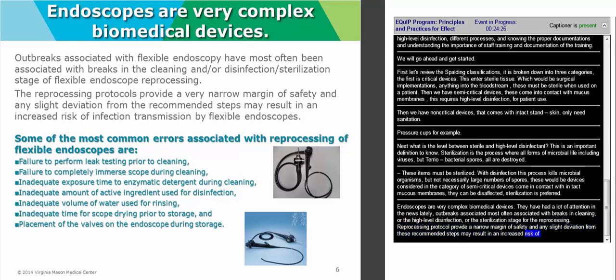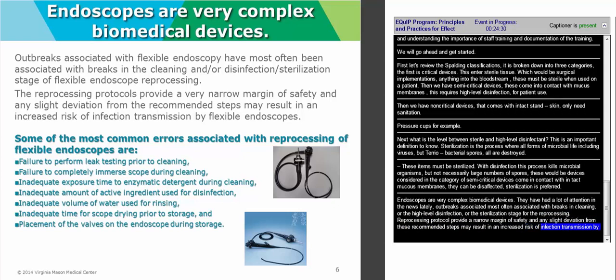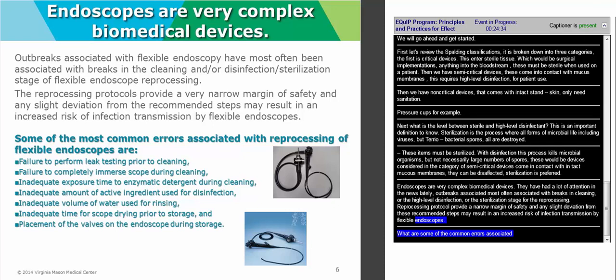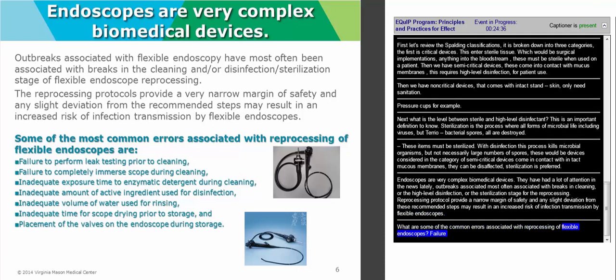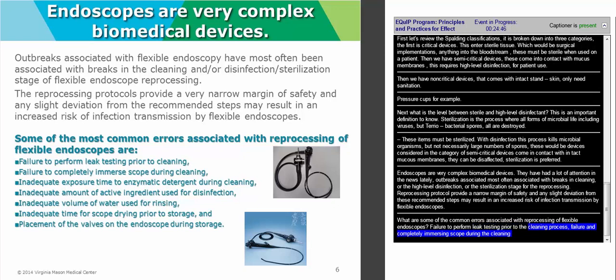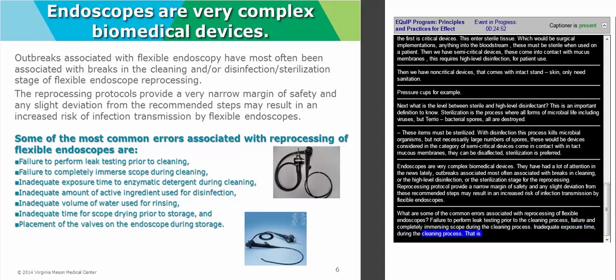Listed here in bullet points are some of the common errors that are associated with reprocessing of flexible endoscopes. Failure to perform leak testing prior to the manual cleaning process. Also failures in completely immersing the endoscope during the manual cleaning process. Inadequate exposure time to enzymatic detergent during the cleaning process. And that's usually gone by, you look at your manufacturer's instructions for use per the detergent that you are using for the correct amount of contact time.